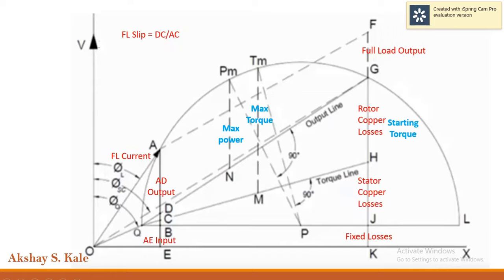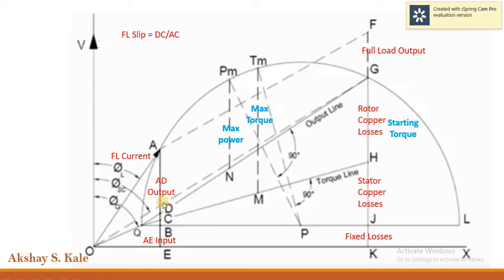The most important part: these are all the parameters you get from the circle diagram. The length of line PmN multiplied by the power scale gives the maximum power. The length of line PM multiplied by the power scale gives the rotor copper losses, the stator copper losses, and the fixed losses. AD is the full load output and AE is the input to the motor. You can also calculate the full load slip: DC divided by AC gives you the full load slip.